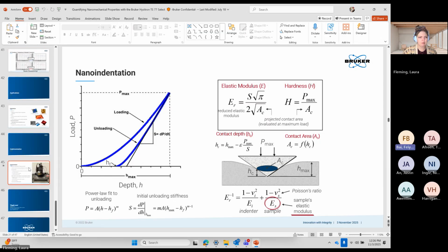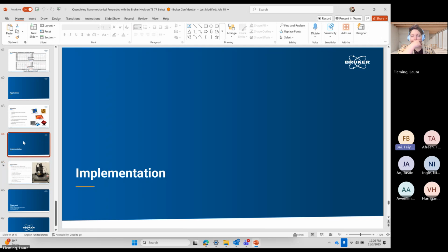One thing before we move further, Laura. Jim, the on-site installation engineer, said that for the hardware of the machine there is an order of turning on, like it's all from up down, right? It's a computer and there are two controllers and then the NI control module. What's important is that the computer is fully turned on before the controllers are. The order of the controllers and the monitor doesn't really matter, but the computer has to be fully on before the controllers can be turned on.